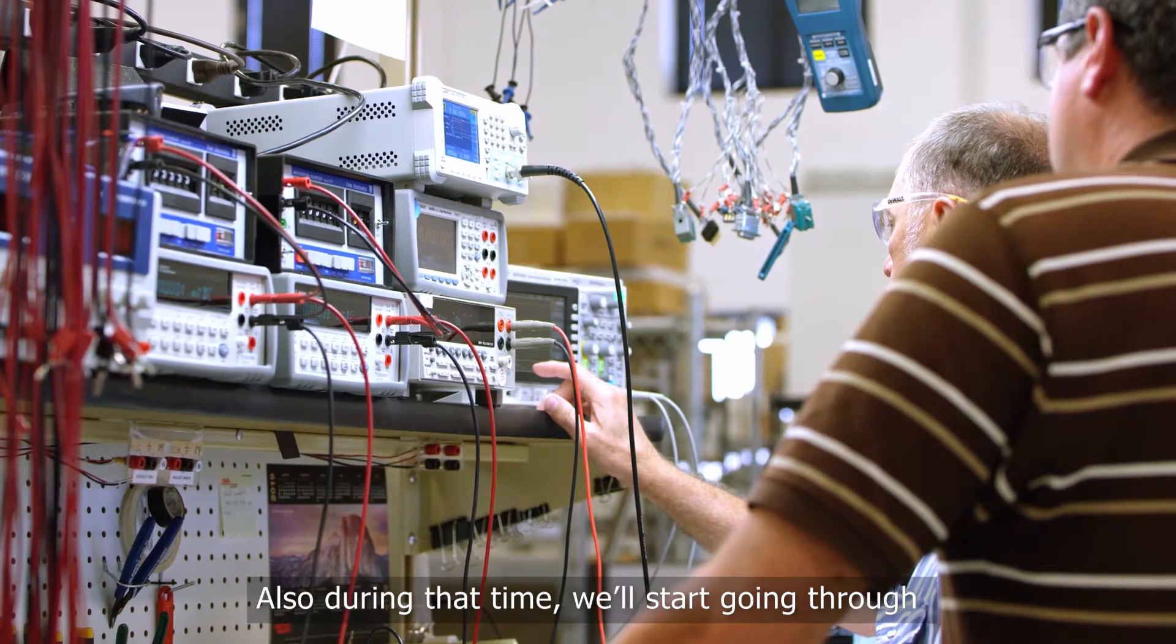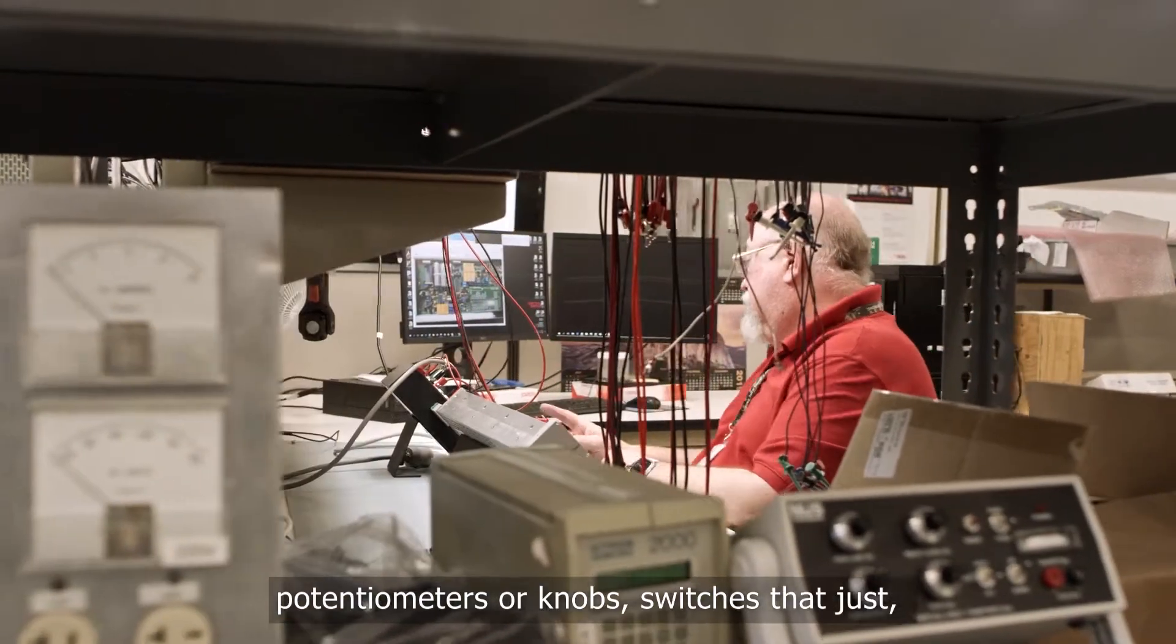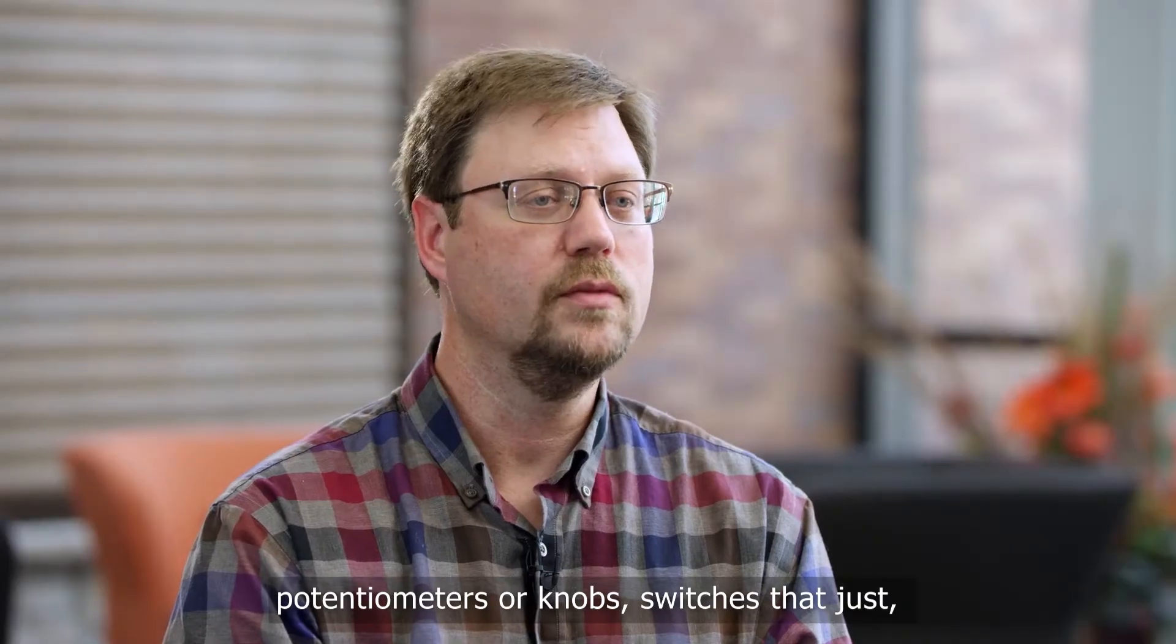Also during that time, we'll start going through and looking for age-sensitive components, equipment that may degrade over time—potentiometers or knobs, switches that just lifetime has been exceeded. We will find replacement parts for those, perform an equivalency to ensure that the part will not affect the operation of the equipment.